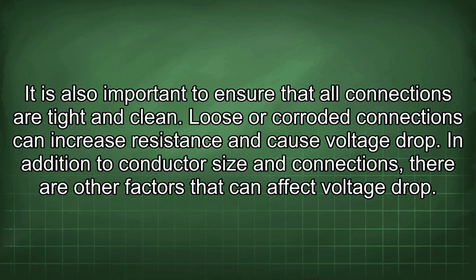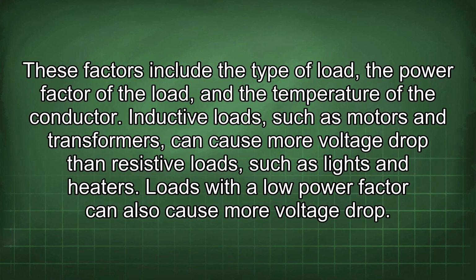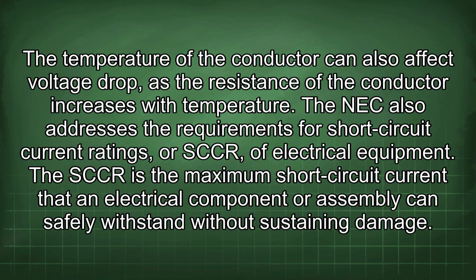In addition to conductor size and connections, there are other factors that can affect voltage drop. These factors include the type of load, the power factor of the load, and the temperature of the conductor. Inductive loads, such as motors and transformers, can cause more voltage drop than resistive loads, such as lights and heaters. Loads with a low power factor can also cause more voltage drop. The temperature of the conductor can also affect voltage drop, as the resistance of the conductor increases with temperature.